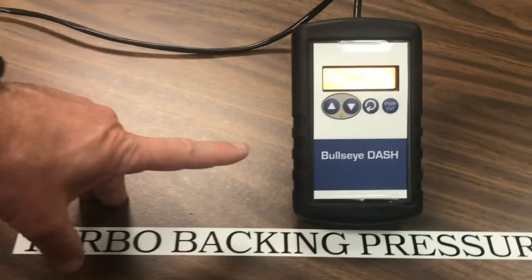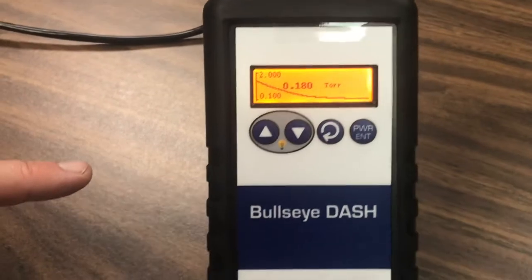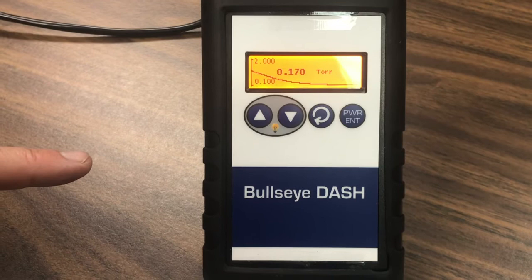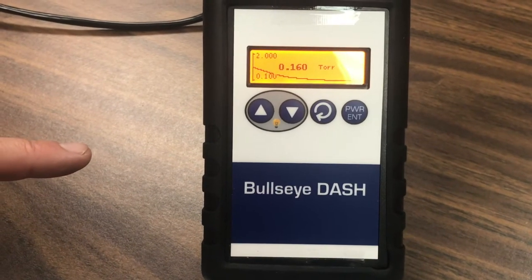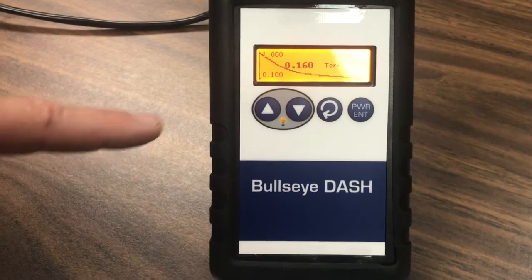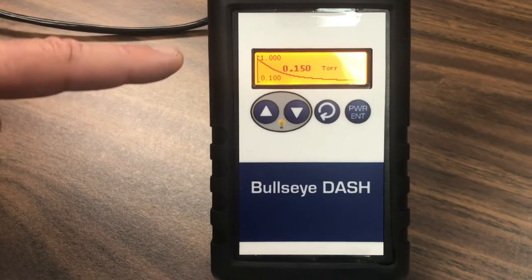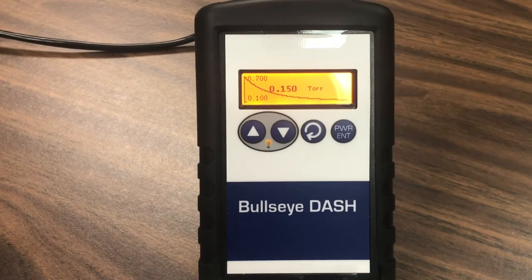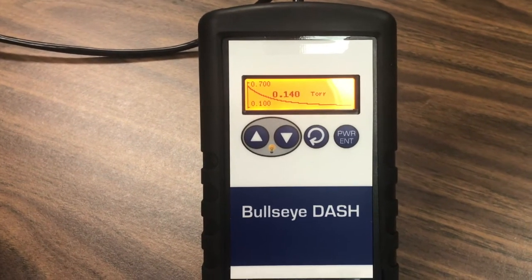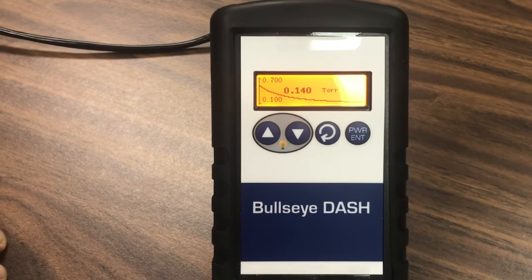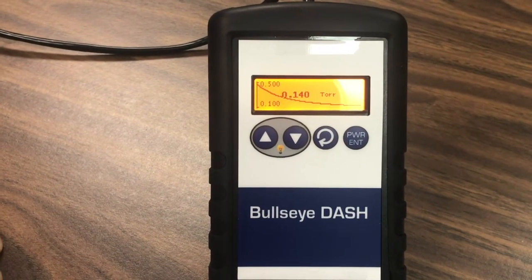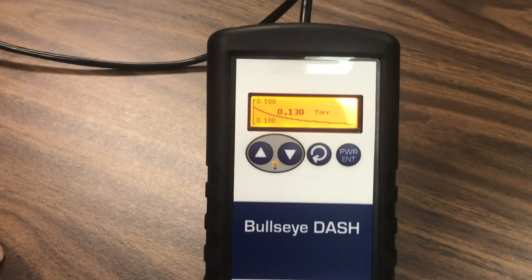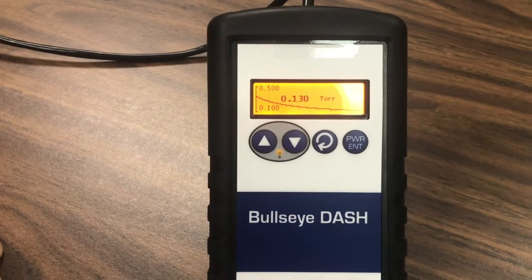Over here, I also chose a line graph because the same pump that's being used to rough out the foreline is also being used to rough out the entire chamber. So I like to see where the foreline is at to make sure that stays below 1 torr. And this is nice because this is actually monitoring the capacitance manometer on the system, and you've got a very accurate depiction of when the turbo pump took over and started bringing that vacuum into that high vacuum range outside the roughing vacuum range. Yep, so for sure, it's a nice demonstration of that.